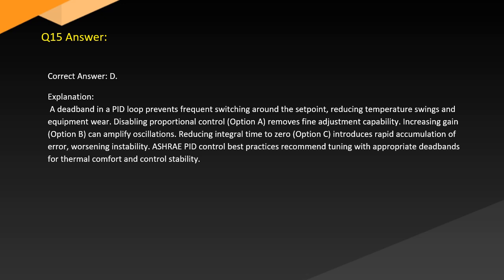Answer. Correct answer: D. Explanation. A deadband in a PID loop prevents frequent switching around the set point, reducing temperature swings and equipment wear. Disabling proportional control, option A, removes fine adjustment capability. Increasing gain, option B, can amplify oscillations. Reducing integral time to 0, option C, introduces rapid accumulation of error, worsening instability. ASHRAE PID control best practices recommend tuning with appropriate deadbands for thermal comfort and control stability.